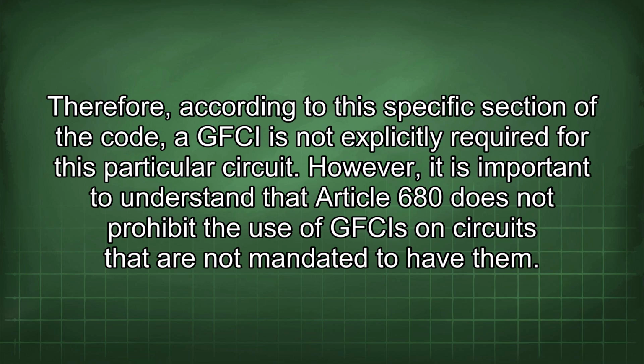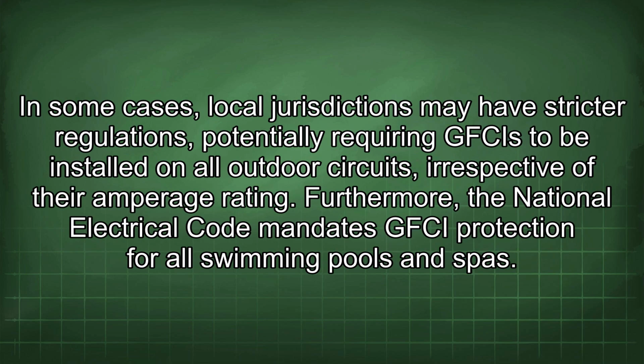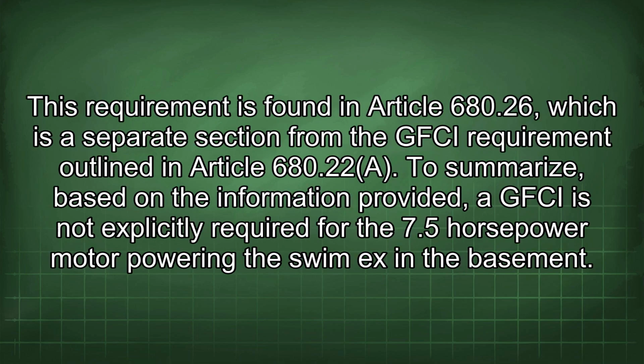However, it is important to understand that Article 680 does not prohibit the use of GFCIs on circuits that are not mandated to have them. In some cases, local jurisdictions may have stricter regulations, potentially requiring GFCIs to be installed on all outdoor circuits, irrespective of their amperage rating. Furthermore, the National Electrical Code mandates GFCI protection for all swimming pools and spas.